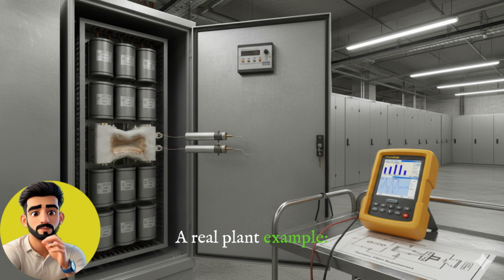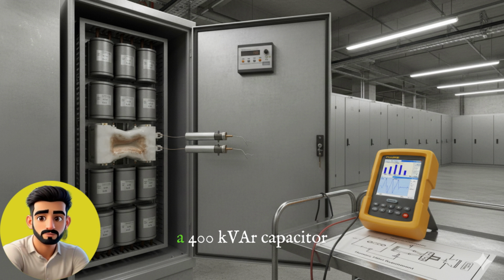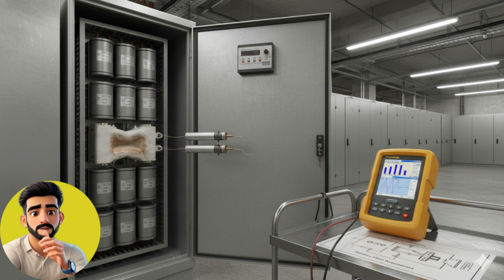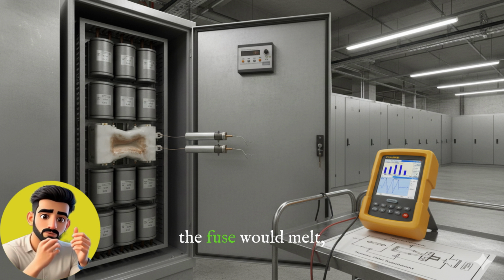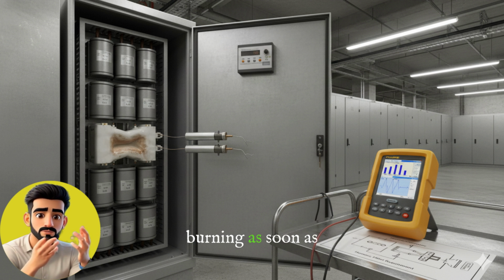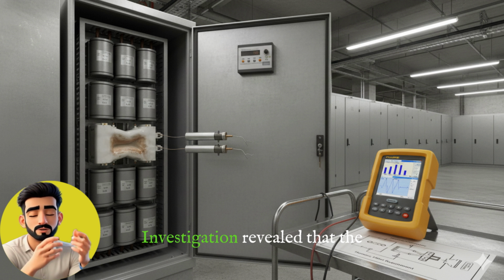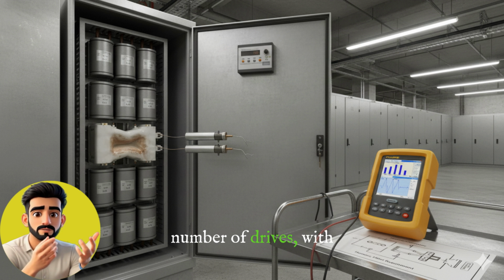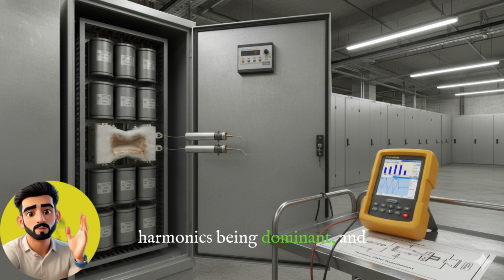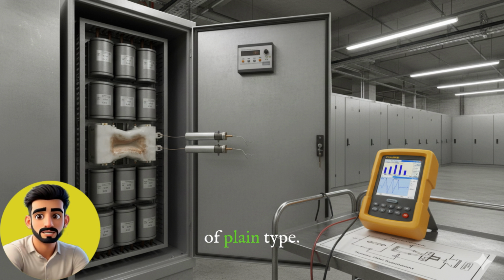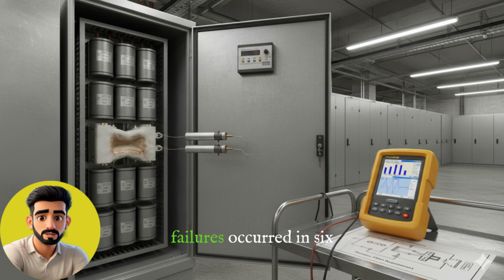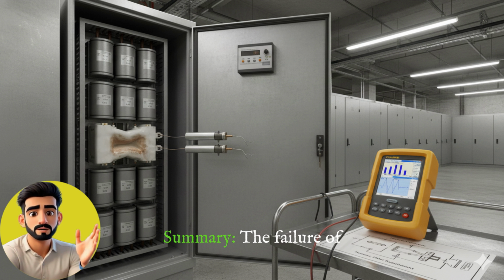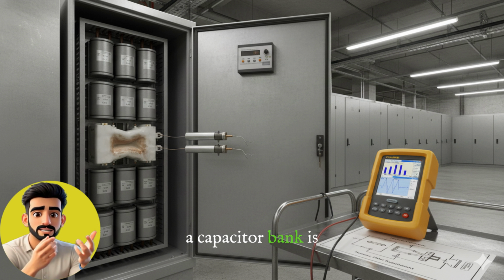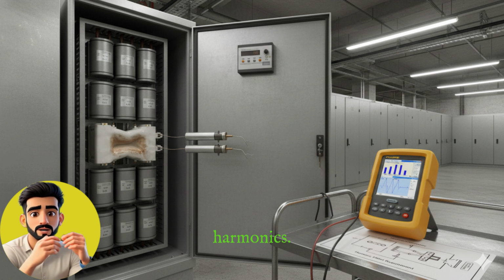A real plant example. In a cement plant, a 400 kilovolt ampere reactive capacitor bank was failing every 12 days. The capacitor would bulge, the fuse would melt, and people would smell burning as soon as they opened the panel. Investigation revealed that the plant had a significant number of drives, with the 5th and 7th harmonics being dominant, and the capacitor bank was of plain type. A series reactor was installed, and thereafter, no failures occurred in 6 months. Summary: the failure of a capacitor bank is less due to overload and more due to harmonics.